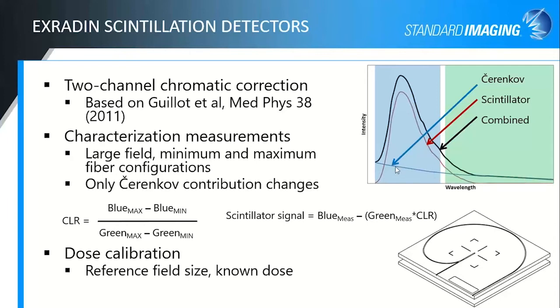Cherenkov is a broad spectrum contaminant light, and so we actually split the total signal into 2 components. We call it the blue channel and the green channel. So blue is primarily the scintillator with Cherenkov, and then the green is primarily Cherenkov with this tail of the scintillation light in it as well. And so in order to characterize the response, you do 2 separate measurements.